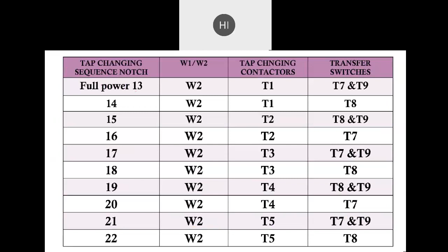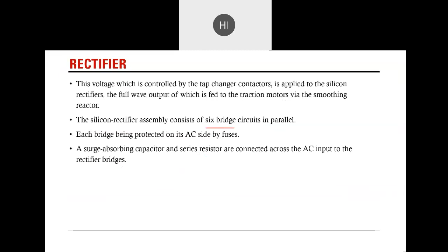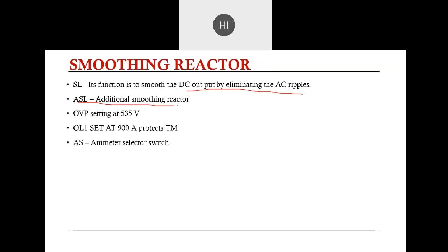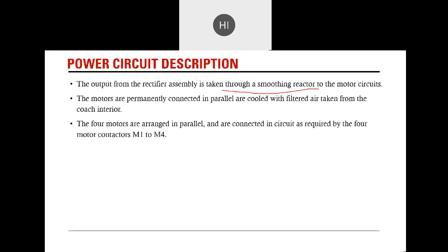अब इसी के बारे में आगे और थोड़ा क्लैरिफिकेशन मैं बताऊंगा. देन रेक्टिफायर हमने पहले ही बोला, वी हैव 6 ब्रिज रेक्टिफायर्स, ओके. सो वी नो दैट द पर्पस ऑफ रेक्टिफायर्स, ओके. एंड फ्रॉम द रेक्टिफायर योर डीसी गोज इनटू अ स्मूथिंग रिएक्टर. स्मूथिंग रिएक्टर क्या करता है? स्मूथिंग रिएक्टर डीसी आउटपुट से it eliminates the AC ripples, and then we also have the additional smoothing reactor also, ठीक है. Then each motor is protected by an overload relay which trips the motor contactor in case of overload, excessive अगर voltage हो गया तो वो motor को trip कर देता है. So we saw here, this is the OL1, OL2, this is the overload relay, okay. It trips the motor if there is any kind of an overload.